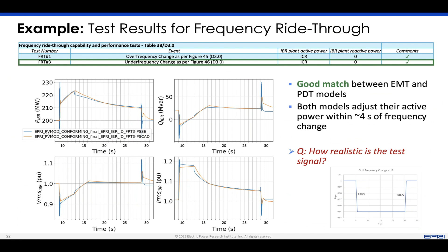To make it more fun, two more slides. We don't have time for it in detail, but the question is, when does it actually make sense to do any of these verifications? We'd say it makes sense as soon as you have validated IBR equipment models and verified IBR plant models, which build on those validated equipment models. You have that early on in the process because you tell your OEM and your plant developer they have to strictly follow all the IEEE 2800 rules. Maybe they use generic models to define the reference responses, and then they guarantee that throughout the engineering process, they verify that their design actually meets these responses.